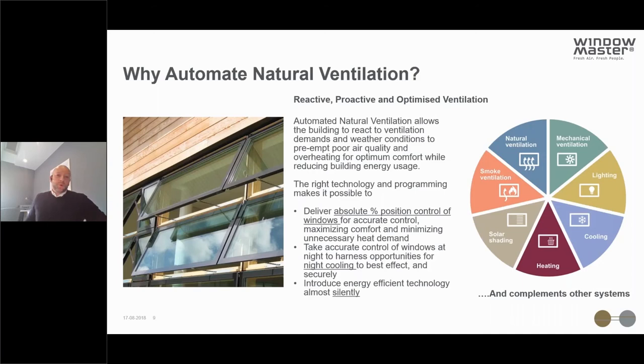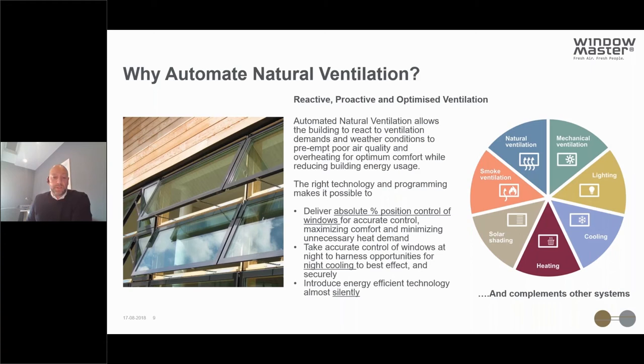Why automate natural ventilation? Simply put, by automating windows we're able to enable the building to be more reactive to demand for ventilation, react to weather conditions, and be much more proactive in preventing overheating and poor air quality. With the right technology we can deliver very fine control, strategies like night cooling and controlled drafts, minimise heat loss in winter, and introduce ventilation almost silently with new technology. It also complements other systems such as solar shading, mechanical ventilation, and cooling.